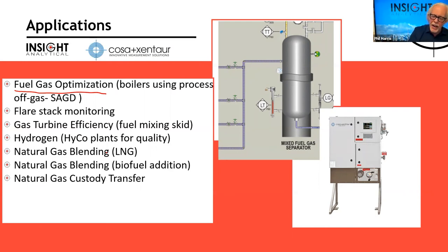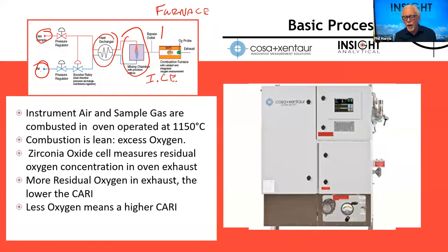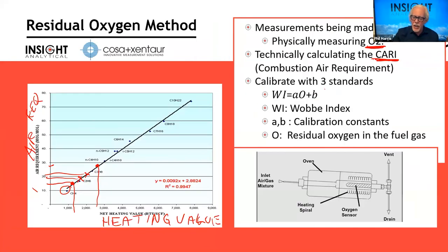If I'm going to go to a flare stack, again, depending on what I've got in my flare, the BTU of the fluid in my flare can change. And this is a common one where we do see hydrogen in the flare gas. So if you've got a varying hydrogen concentration, there's two approaches. If it doesn't vary too much, if it only varies by about 10%, you can go back to these three calibration standards and try to bracket that hydrogen variation and make sure the analyzer is calibrated to work over those ranges.